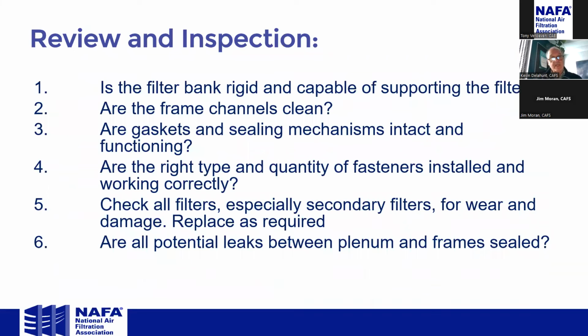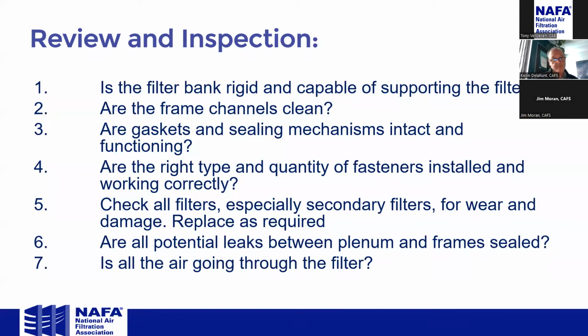What the inspection entails is that we look at the filter bank. Is it still structurally sound? Are the channels clean? Are the gaskets functioning and the sealing mechanisms intact and operating? And are the right type and quantity of fasteners installed and working correctly? We check all filters, especially secondary filters, for wear and damage and replace as required, and try to identify any chance of potential leaks between the plenum and around the filter frames. Bottom line, we want to guarantee that all the air is going through the filter.